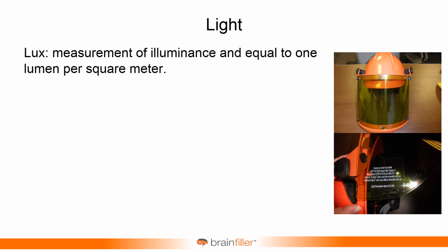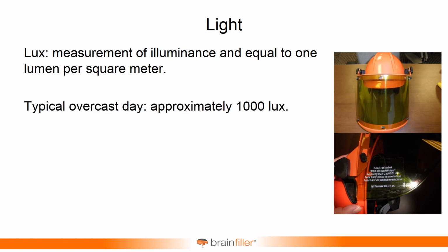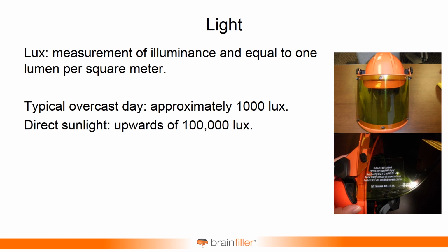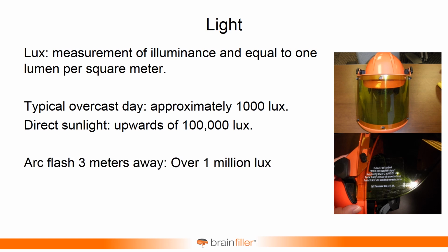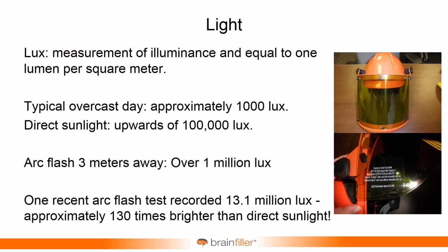And so to give you some idea, some basic frames of reference for what we're talking about. Around 1,000 lux is a typical overcast day. You go up to 100,000 lux, and that's a really bright, direct sunlit day. So that gives you a frame of reference. Now, from some of the arc flash tests, 3 meters away, there have been recordings of over 1 million lux. And there was one that actually went up to a little over 13 million lux, over 130 times brighter than the sun. That's going to be a tough one. And yes, light is one of the hazards.